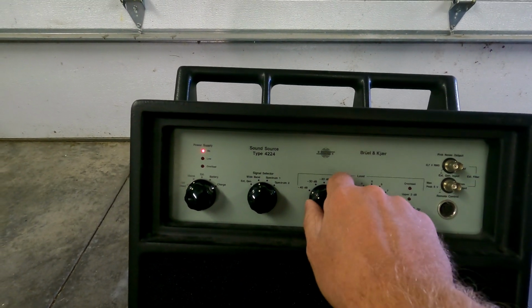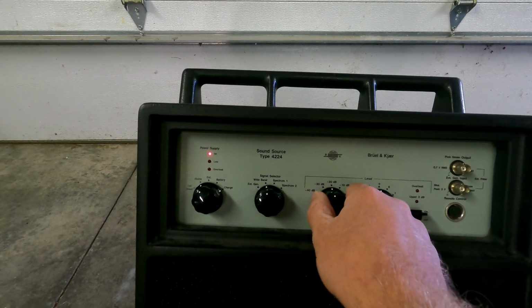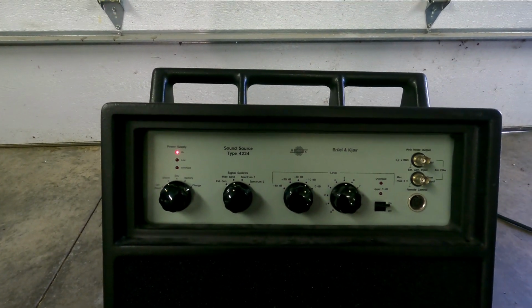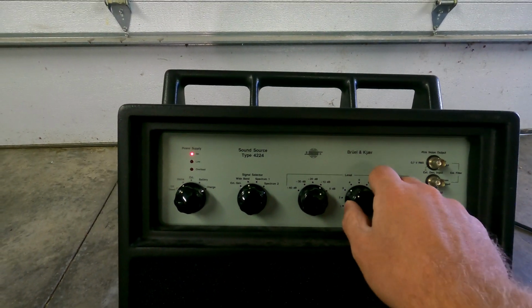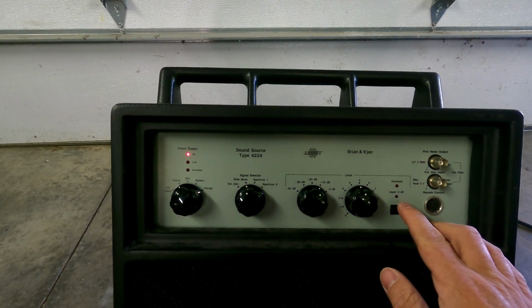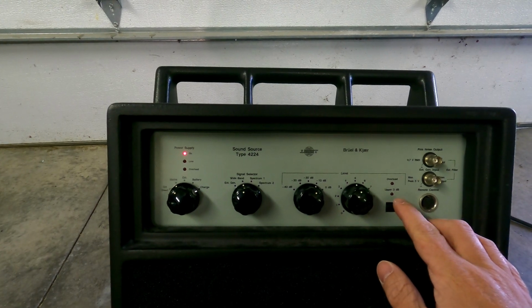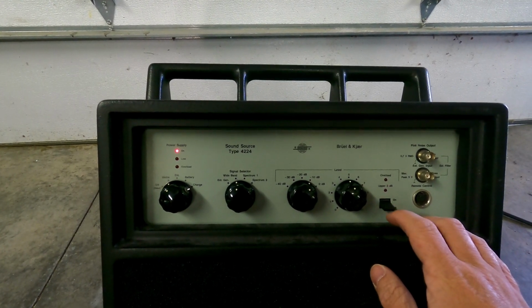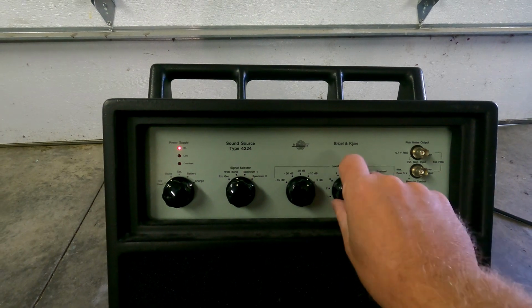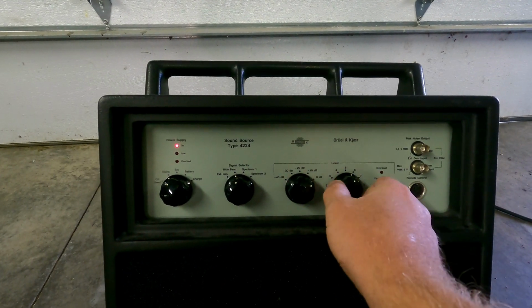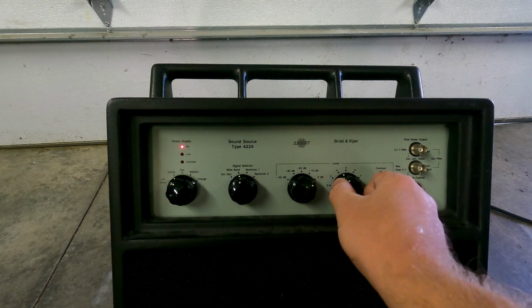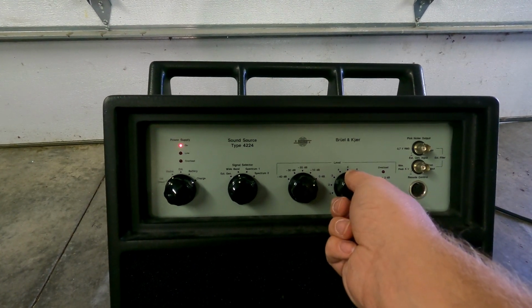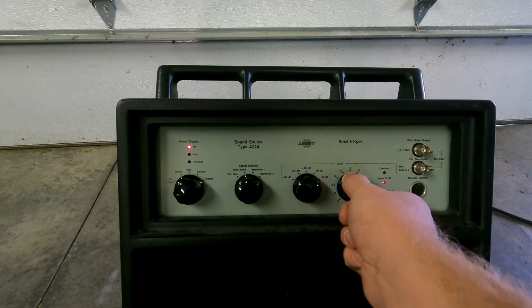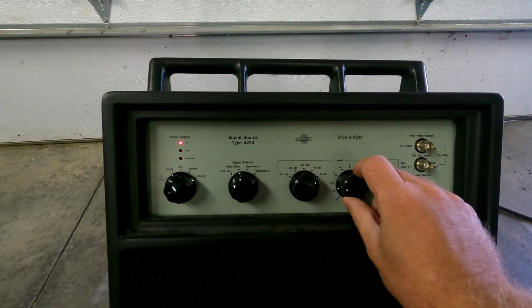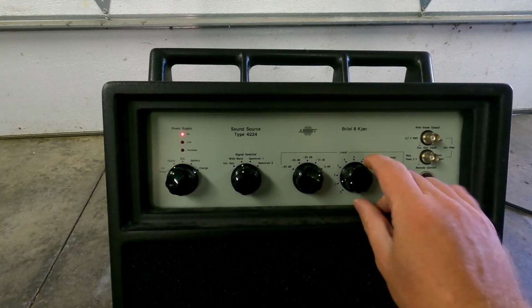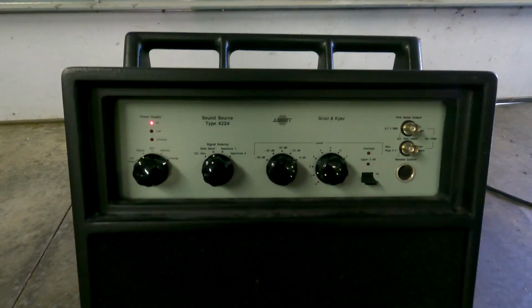So the type of noise this thing makes is called pink noise. This is really useful because it offers equal power in each 1/3 octave band, which is useful for things like building acoustics measurements, where we want to measure how much sound transmits through a wall, or for measuring reverberation time in spaces. This all-in-one device, which also has an external input, was very useful for a lot of building acoustics work, where it just had a known signal it made, and could turn on and off that loud noise source all in one compact package.